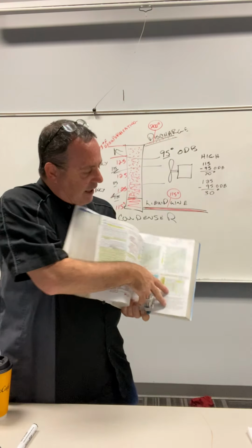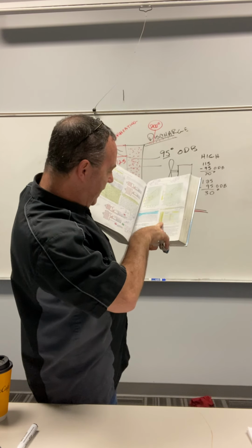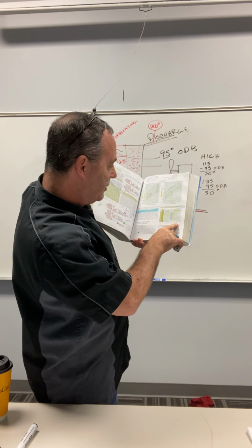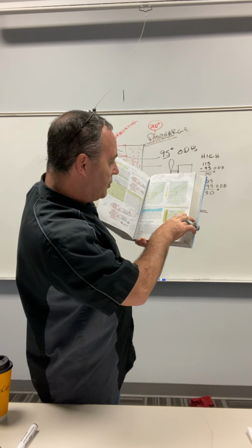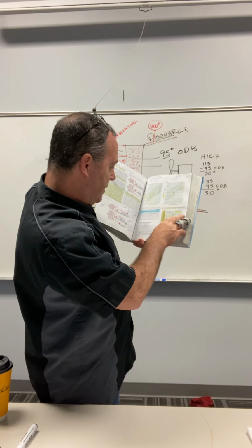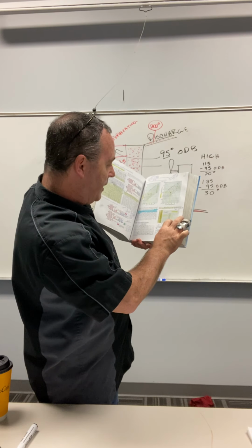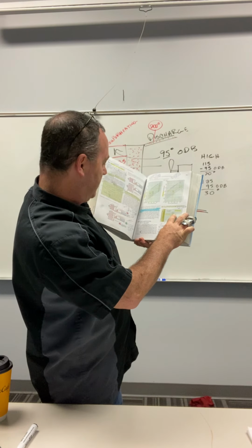This one down here says, if you follow along in your book, over here you have your liquid line pressure. Over here is your compressor suction line. And here it says temperature outside air. Once again, let's say we got 250 head and a 70-pound suction on a 95-degree day. That'd be charged correctly.